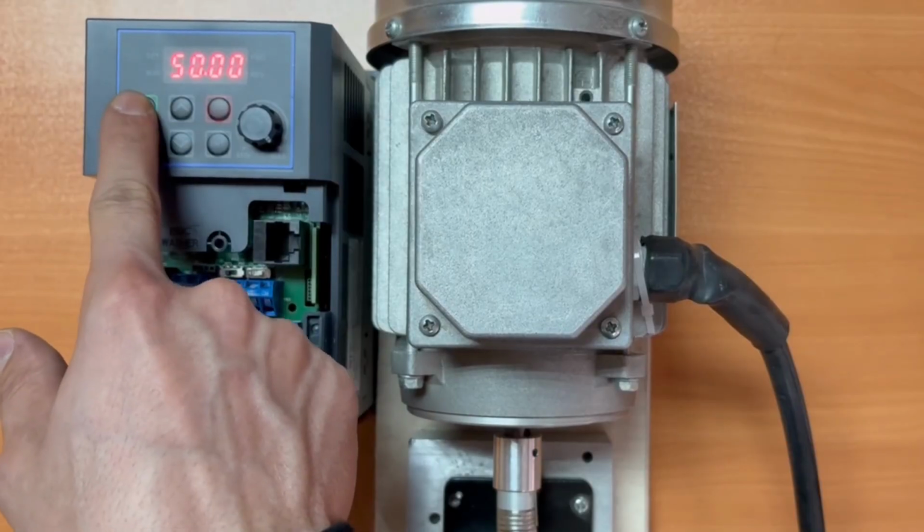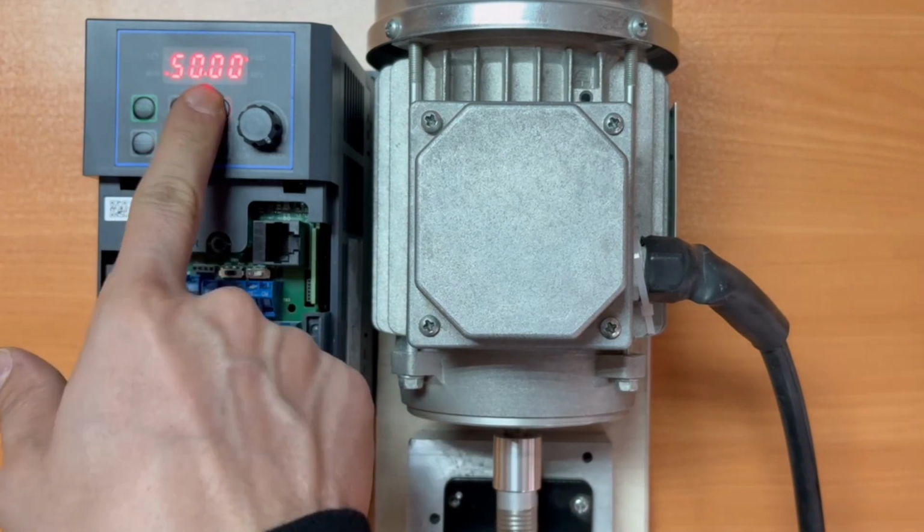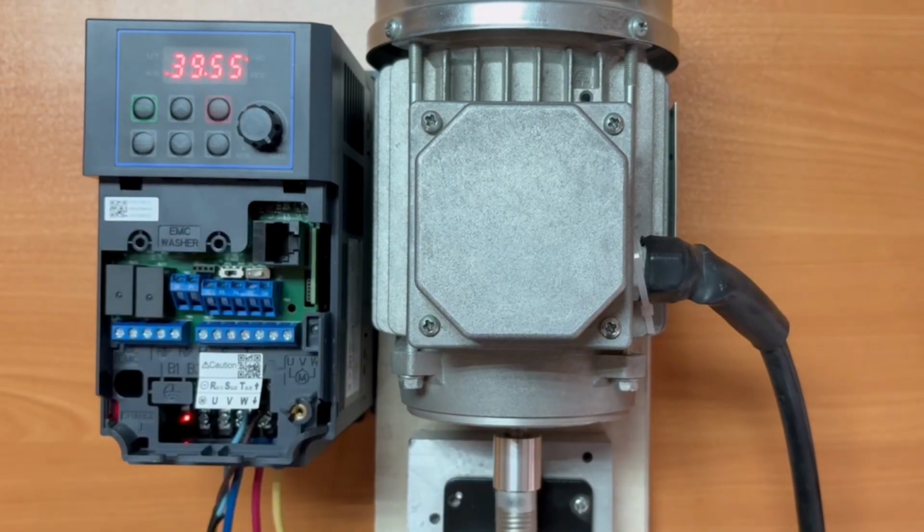Now I'll start my VFD. I wait for it to reach a frequency of 50. Now if I issue the stop command, it should take 10 seconds to go from a frequency of 50 to a frequency of 0. I'm going to stop it now. It takes the duration of 10 seconds, and in the end, my electric motor stops. This was the stop using the deceleration time.